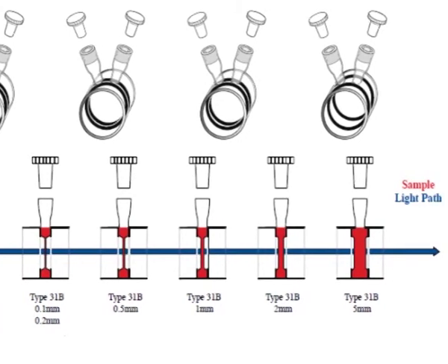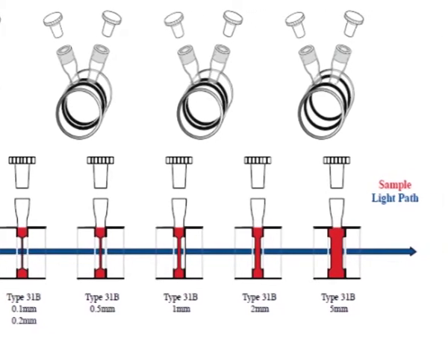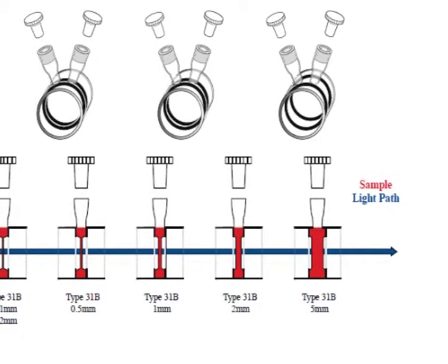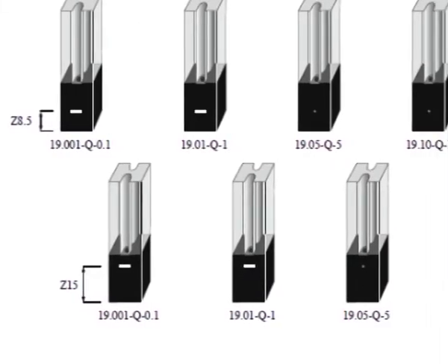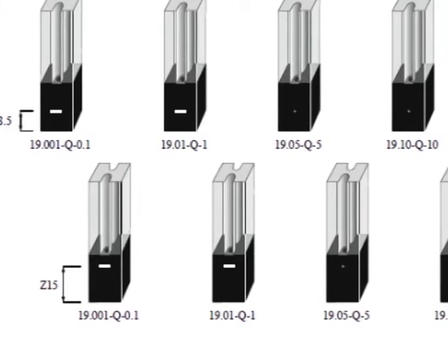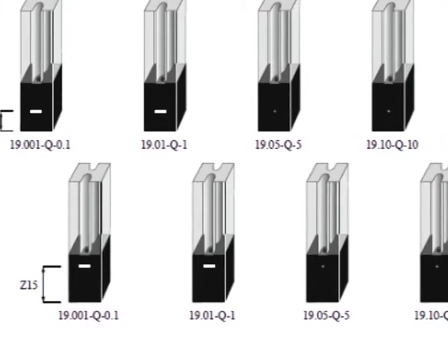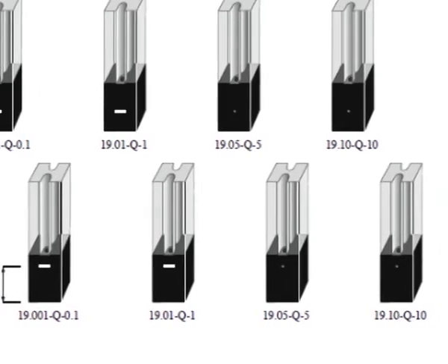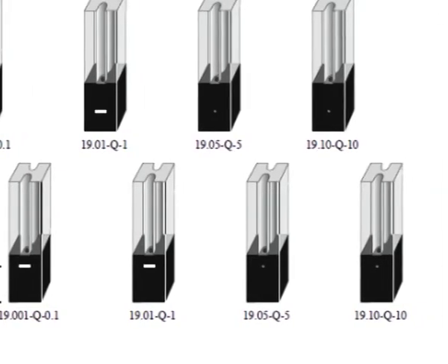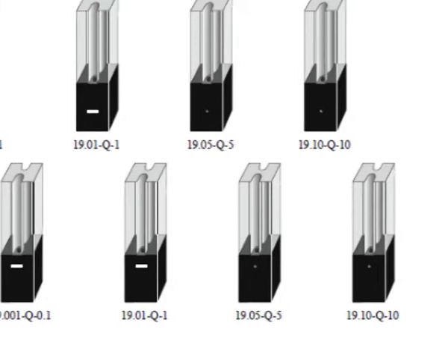Samples for UV or visible spectrophotometry are most often liquids, although the absorbance of gases and even of solids can also be measured. Samples are placed in a transparent cell known as a cuvette. Cuvettes are typically rectangular in shape, commonly with an internal width of 1 centimeter. This width becomes the path length in the Beer-Lambert law.